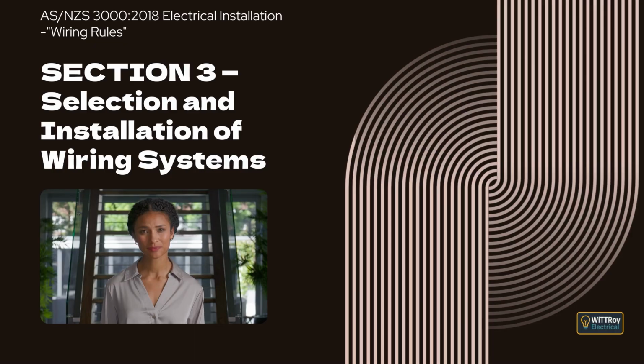Clause 3.9.3.2 Suspended ceilings. This clause explains that wiring systems in suspended ceilings may be supported by the ceiling system unless the ceiling manufacturer does not allow it. Where cables are in contact with conductive ceiling supports, additional mechanical protection is required. Wiring above suspended ceilings must be fixed at suitable intervals to prevent sagging. The clause clarifies that timber ceiling systems covered by other standards are not included.